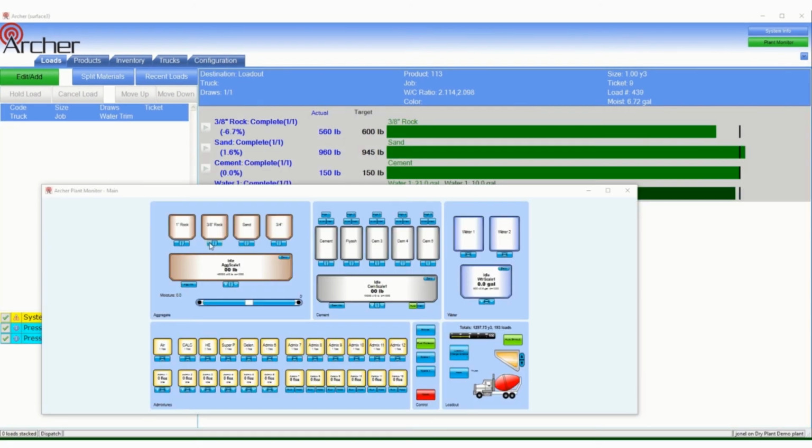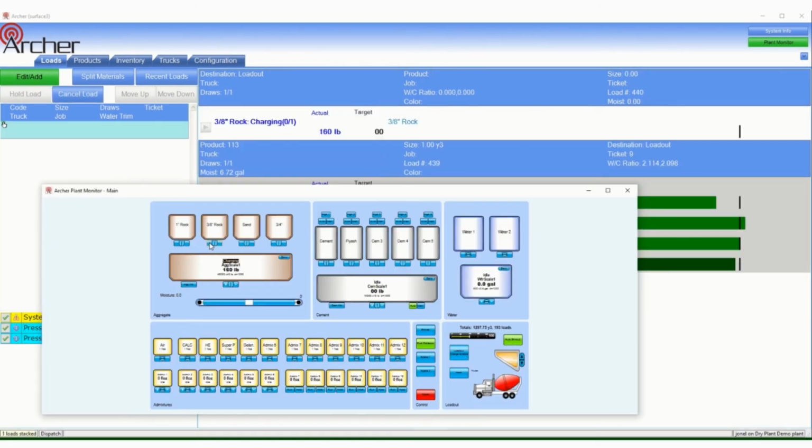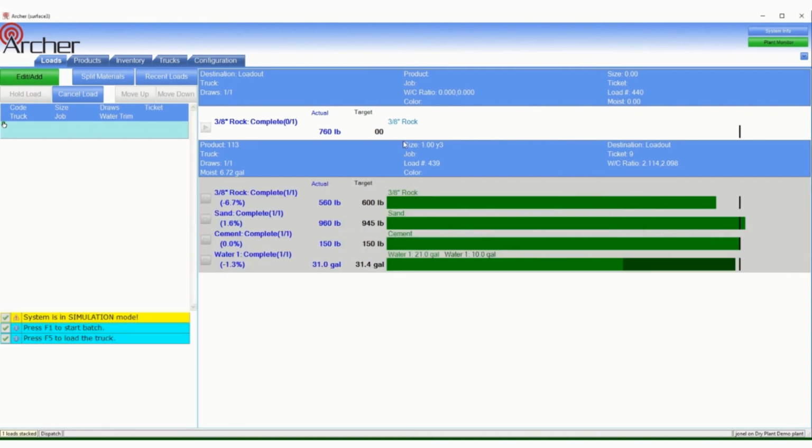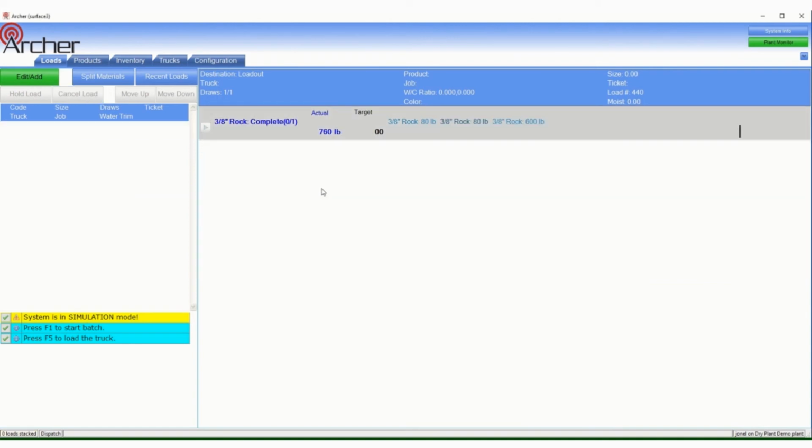If a material is filled manually, this will change the material status to holding manual and enable the red Acknowledge button. To continue batching, you will need to finish charging the scale manually with the selected material or materials. You then need to click the red Acknowledge button, which puts the material into a Weight Inspect checkpoint. Clicking the button again moves on to the next material, if any, and the batch cycle will proceed.